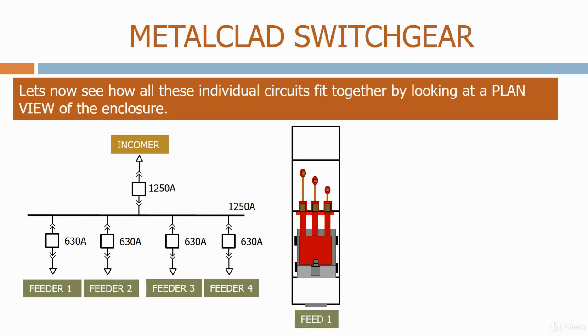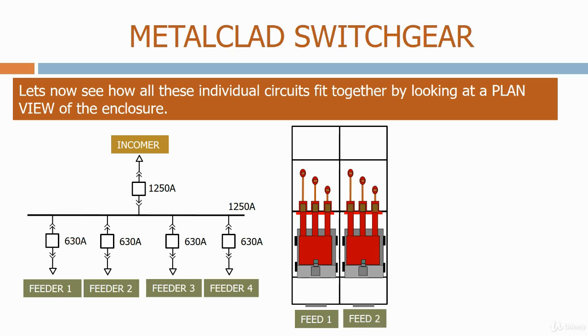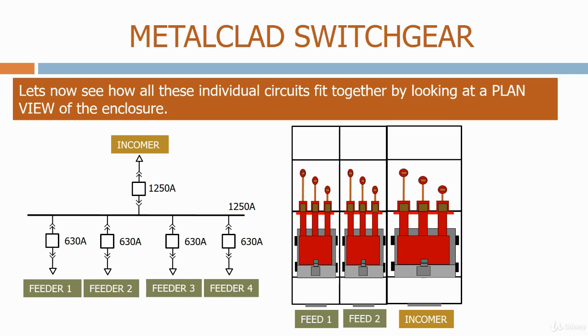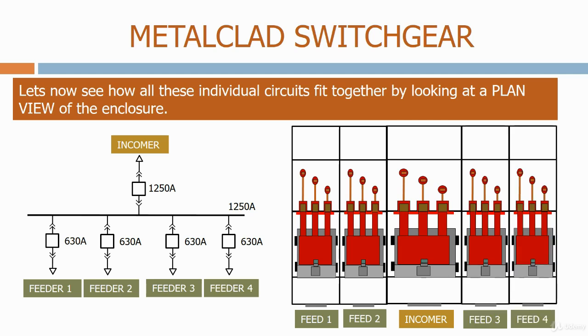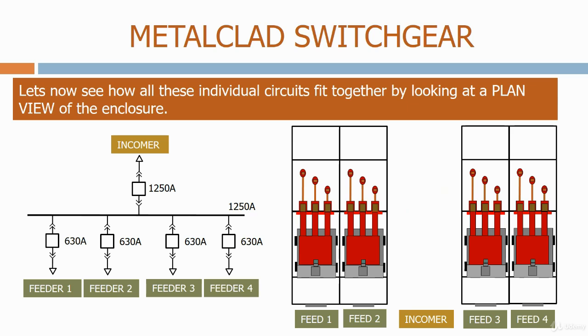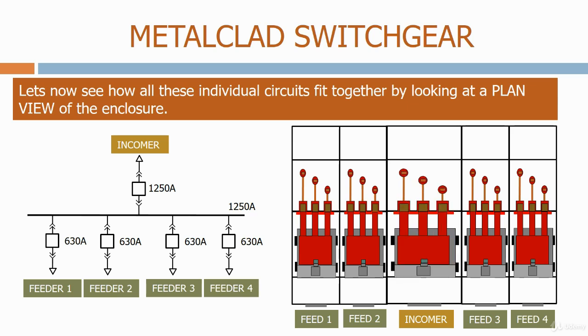Firstly, we have the 630 amp feeder, with the circuit breaker chamber at the front and the bus bar chamber at the back. Let's now add the other circuits. As you would expect, the incomer is rated at 1250 amps, and therefore it's physically bigger than the 630 amp feeder circuits. To connect all the circuits together, we run a red, yellow and blue bus bar along the bus bar chambers. We've now implemented the circuit on the single line diagram.